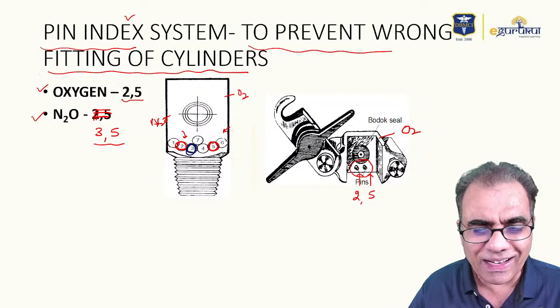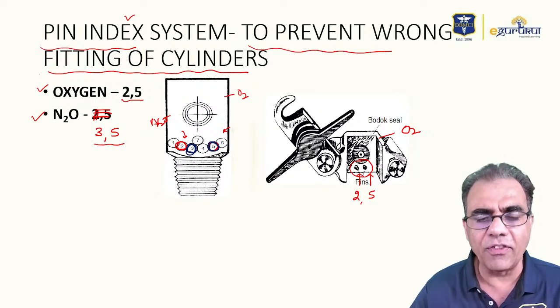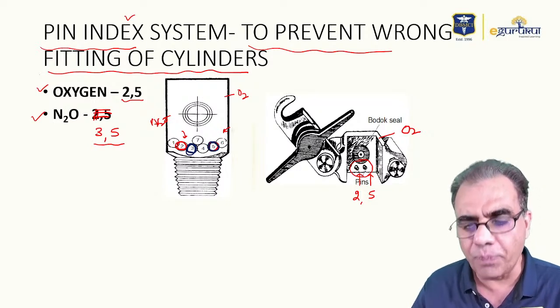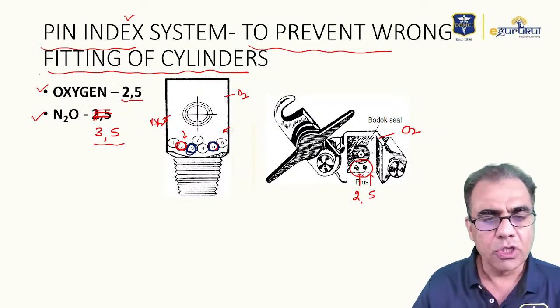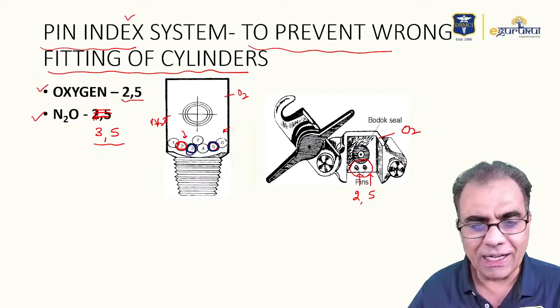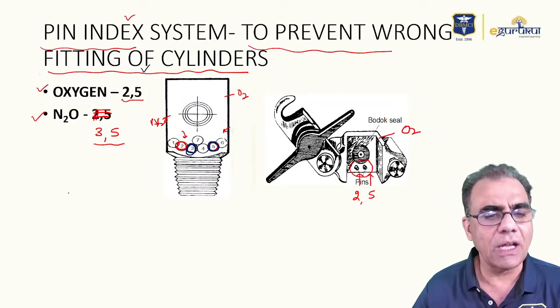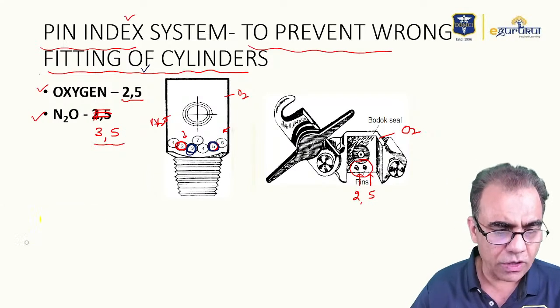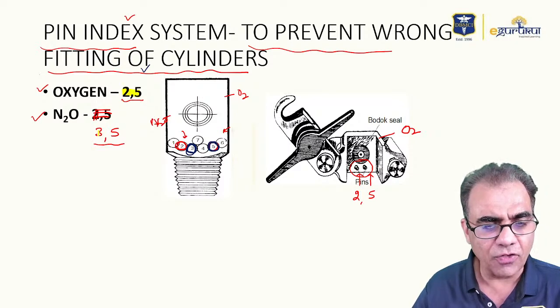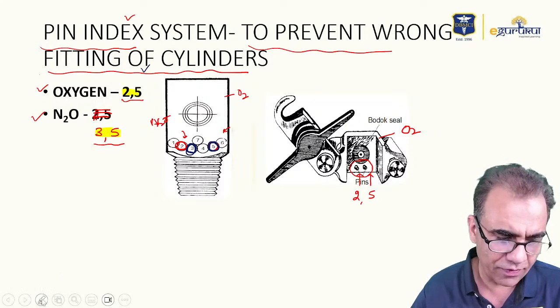So you cannot fit a cylinder with the holes at 3 and 5 at the position of pins at 2 and 5. So the pin index system is to prevent wrong fitting of cylinders to the anesthesia machine, and the pin index position for oxygen is 2, 5, and that of nitrous oxide is 3 and 5.